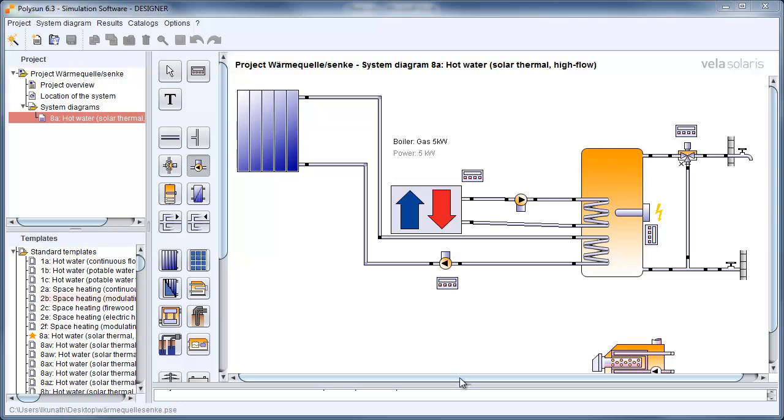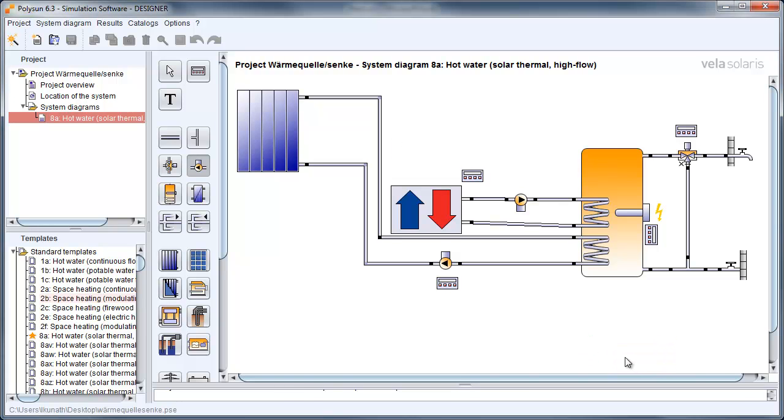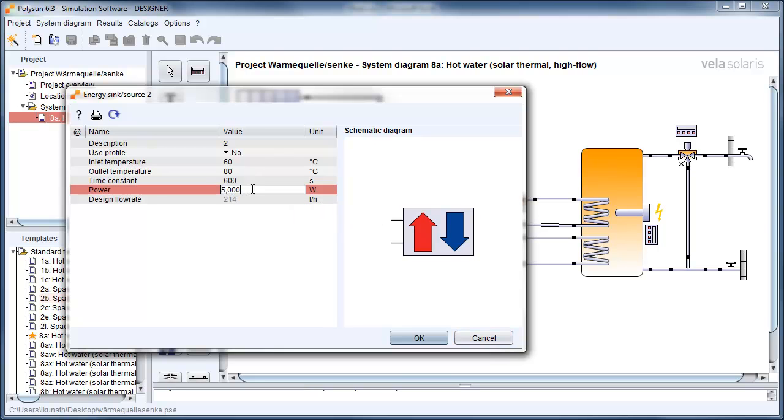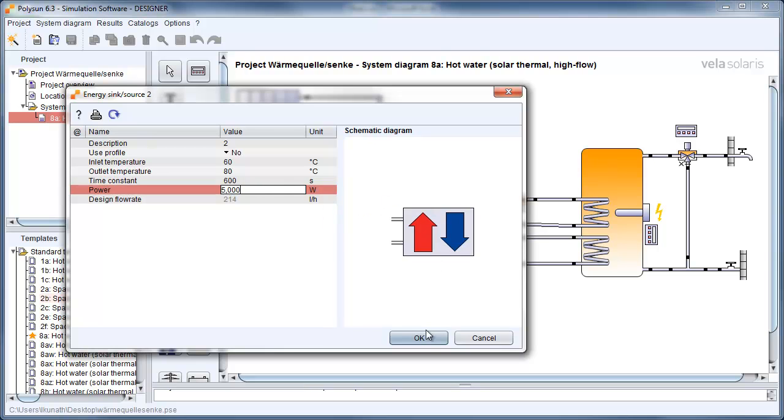Now it's time to delete the gas burner and have a look at the settings for the heat source. Double click on the heat source and define the inlet and outlet temperature. Please don't forget to set the rated power demand for the heat source. I think 5 kW is okay for this system.